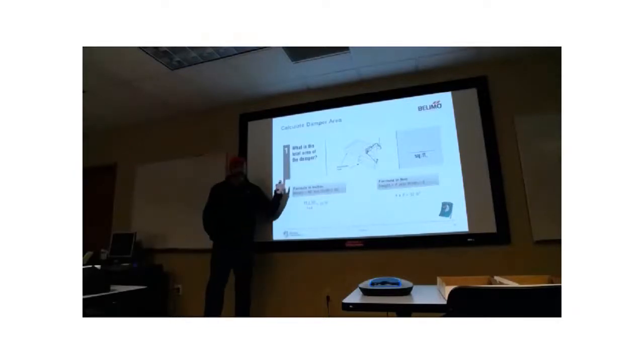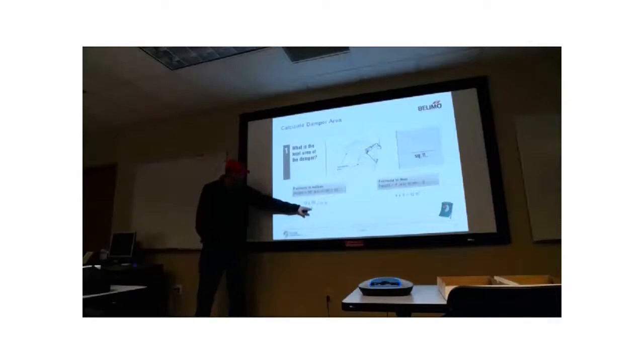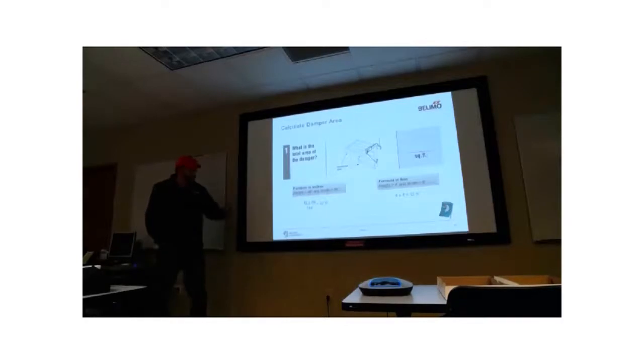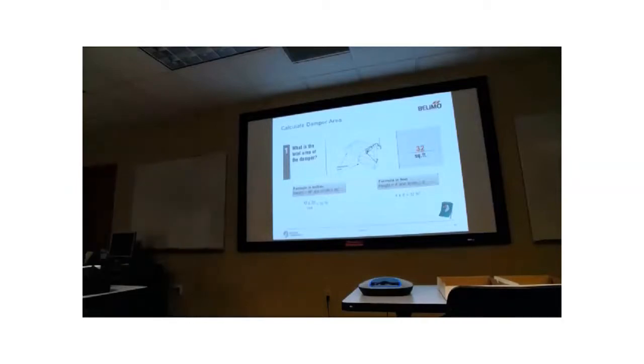The first thing we're going to do is figure out the area of the damper. So in this case, we have a 48 by 96 damper. That's in inches, right? So in order to convert that to square feet, what do we do? We divide by 144, right? Because there's 144 square inches in a square foot. If you know what a 48 by 96 is, you say, I know what that is. That's a 4 by 8. That's a 4 by 8 damper. So our first fill-in, in the upper right on page 9, is 32 square feet.